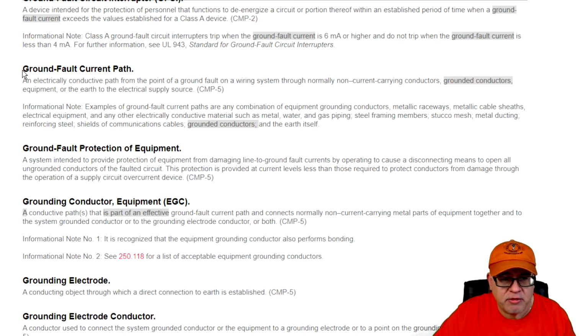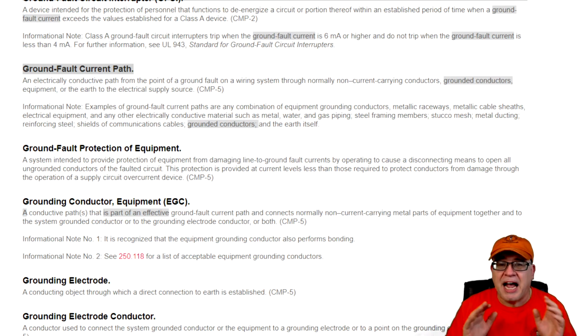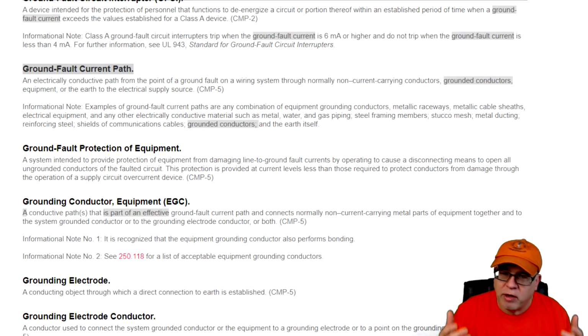All right, next, ground fault current path. Ground fault current path is critical for the operation of overcurrent devices. We size equipment grounding conductors based on ground fault current having a low impedance path. That's why we tie metal parts together. That's why the raceways are done a certain way. That's why we put equipment grounding conductors in. That's why we have equipment bonding jumpers over the devices. This is why we do all this, because we want to establish this low impedance ground fault current path, right?